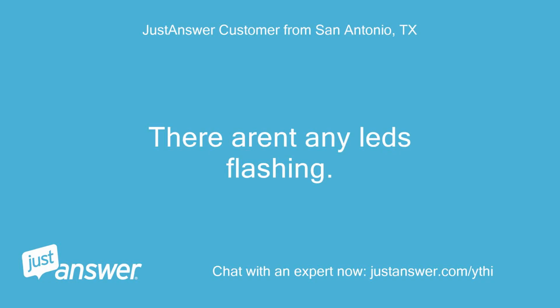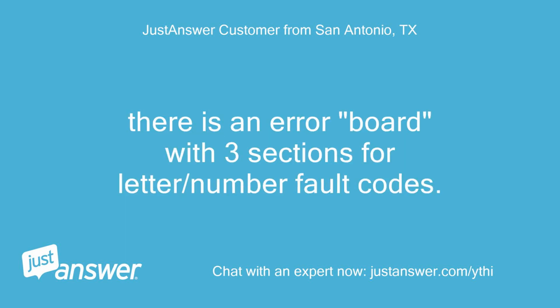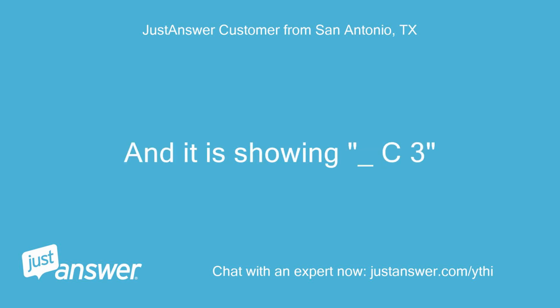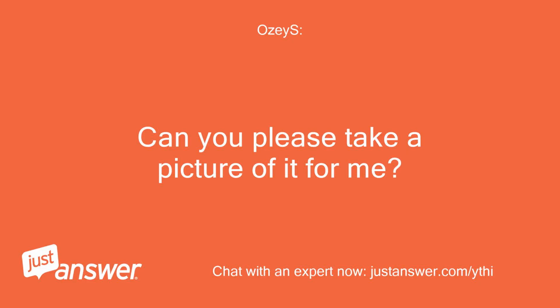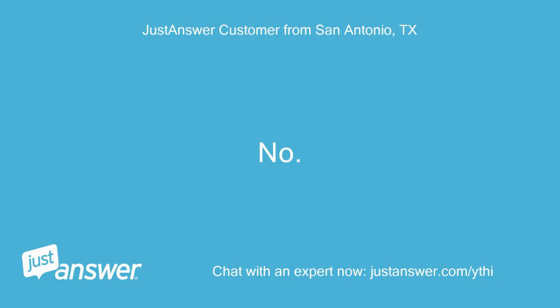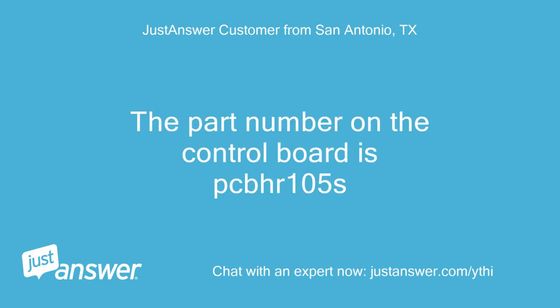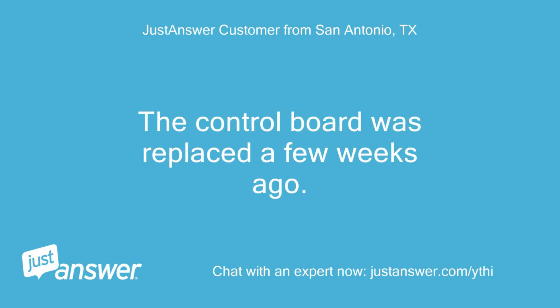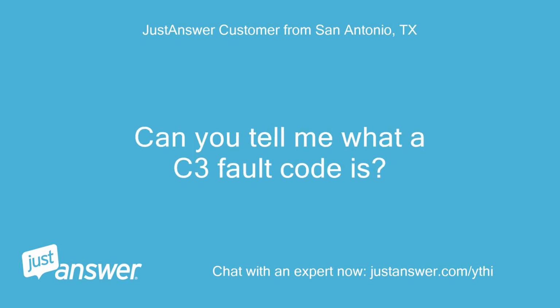There aren't any LEDs flashing. There is an error board with 3 sections for letter/number fault codes. And it is showing _C3. Can you please take a picture of it for me? No. And not with a unit. The part number on the control board is PCBHR105S. The control board was replaced a few weeks ago. Can you tell me what a C3 fault code is?